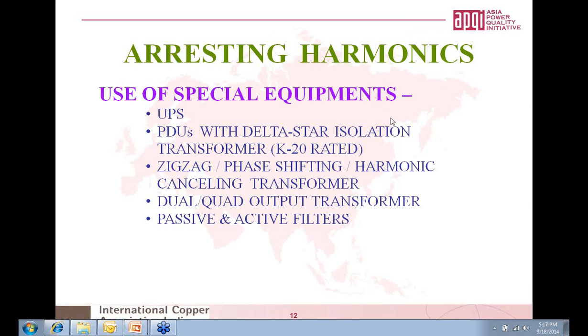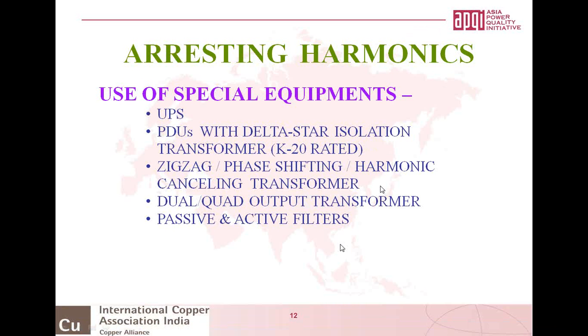Although UPS itself produces harmonics, the new generation of UPS produces a very low amount of harmonics, never higher than 5%. Then there are PDUs with delta-star isolation transformers which can be used to arrest harmonics produced by any of the SMPS based loads. Then there are zigzag and phase shifting harmonic cancelling transformers which can be used in various installations, including factories. And there are dual and quad output transformers, and there are passive and active filters that can be used, which were earlier also spoken of as a case study, and they have been used very effectively.